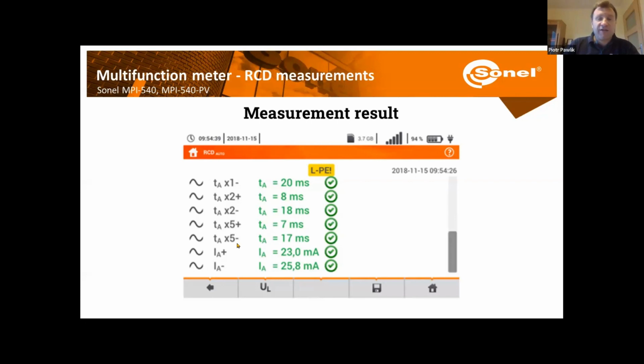Further on, we can check the RCD with different shapes of the current signals. Well, here we can see only the sine wave, but once we move the bar up, then for types A, F, or B, we would be able to see that the RCD was tested with all different shapes of signals. And also we can change the polarization of the signal, depending on whether we have a minus or a plus here at the end. So in case of a sine wave, minus starts with the falling slope and plus starts with the rising slope. And in case of pulsating or DC, that's just the polarization.